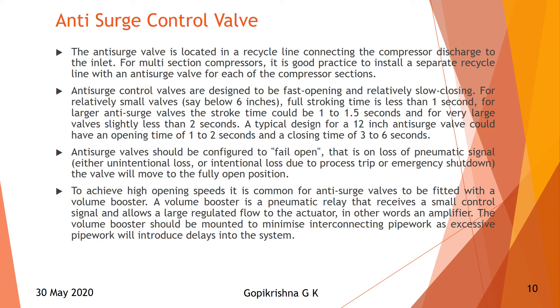The anti-surge control valve is located in a recycle line connecting the compressor discharge to the inlet. For a multi-section compressor, it is good practice to have separate recycle lines for individual anti-surge compressor sections. Anti-surge control valves are designed to be fast opening and relatively slow closing — that is a key point.